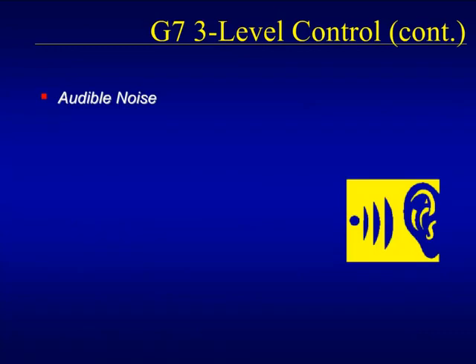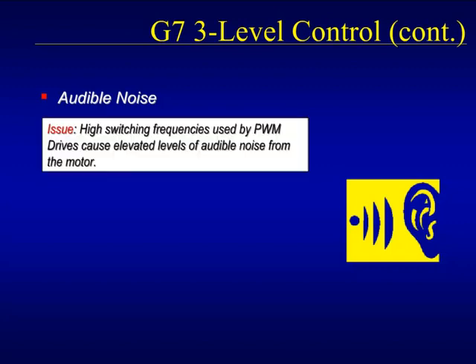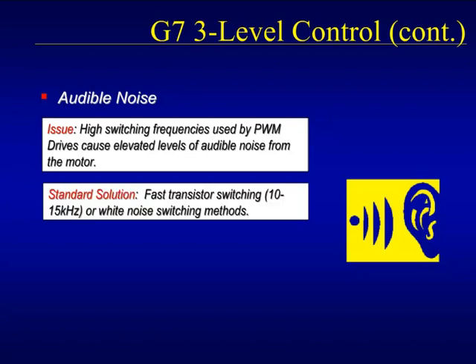The last topic related to three-level control that we will mention is the effects on audible motor noise. It is no secret that operating a motor with the PWM drive will produce significant levels of noise from the motor that can annoy and irritate some humans that are working around the equipment. The only standard way to decrease the audible noise is to increase the PWM switching frequency out of the range of human hearing.